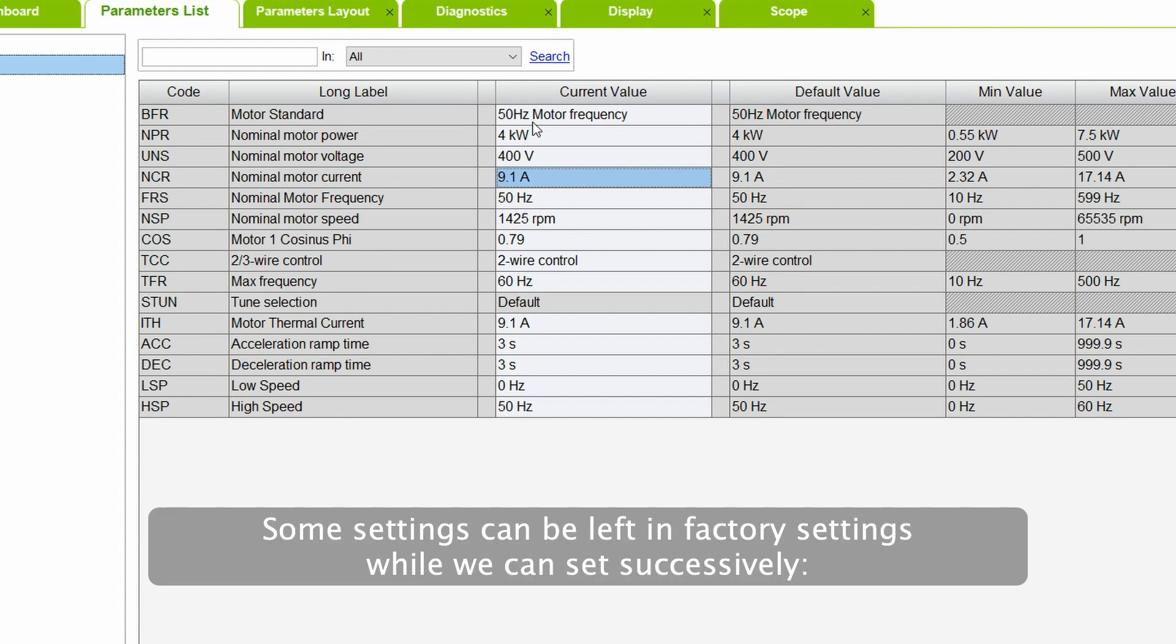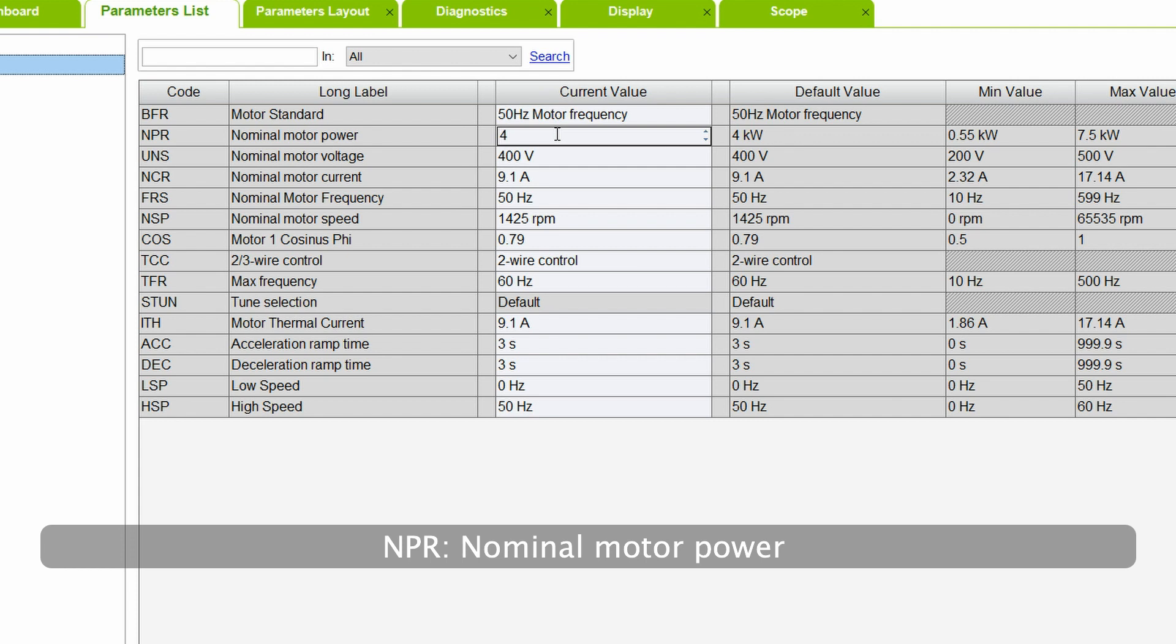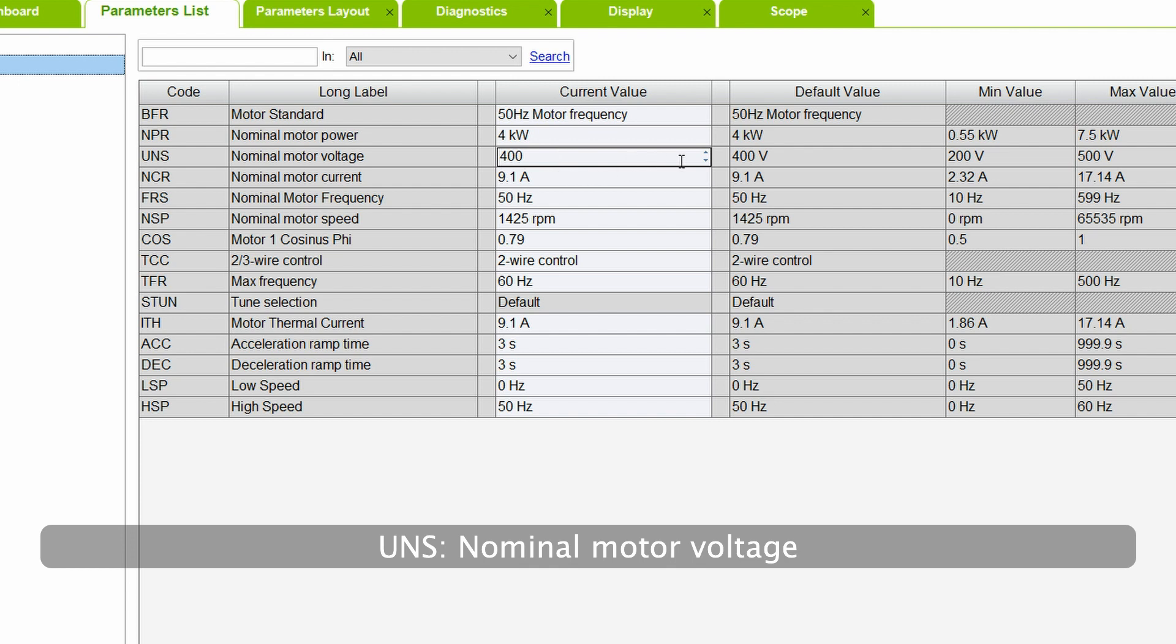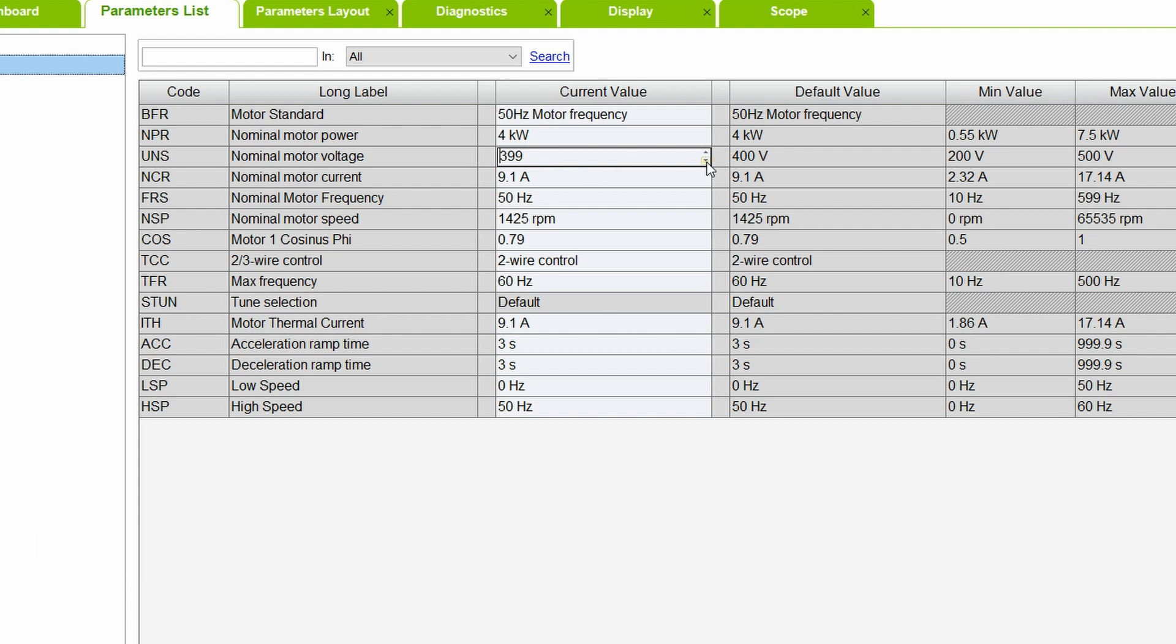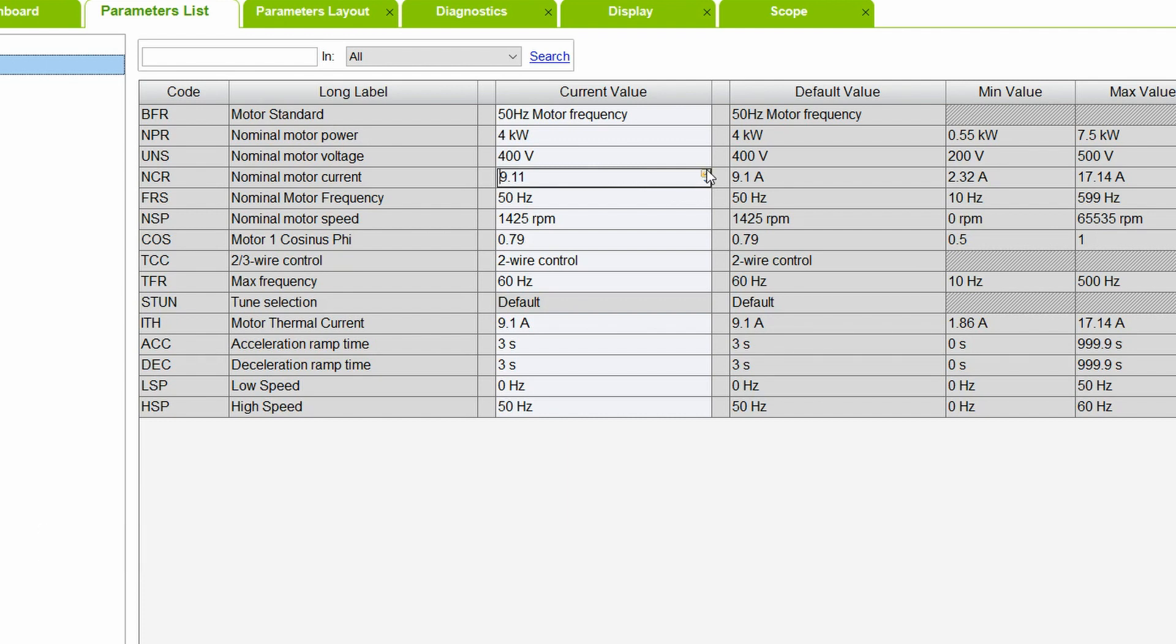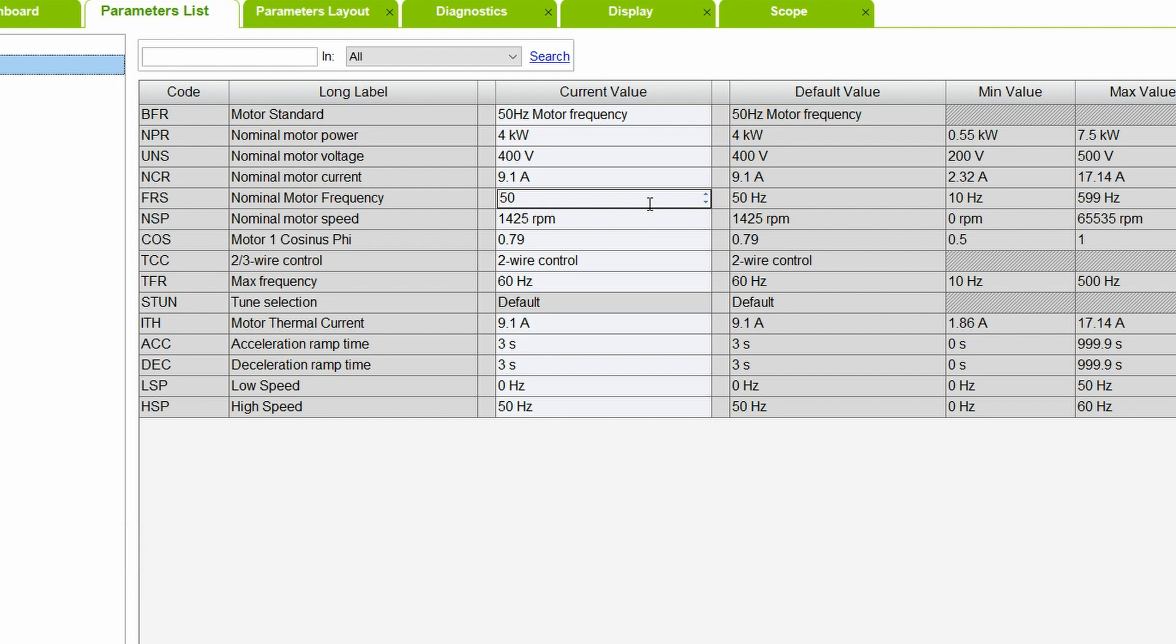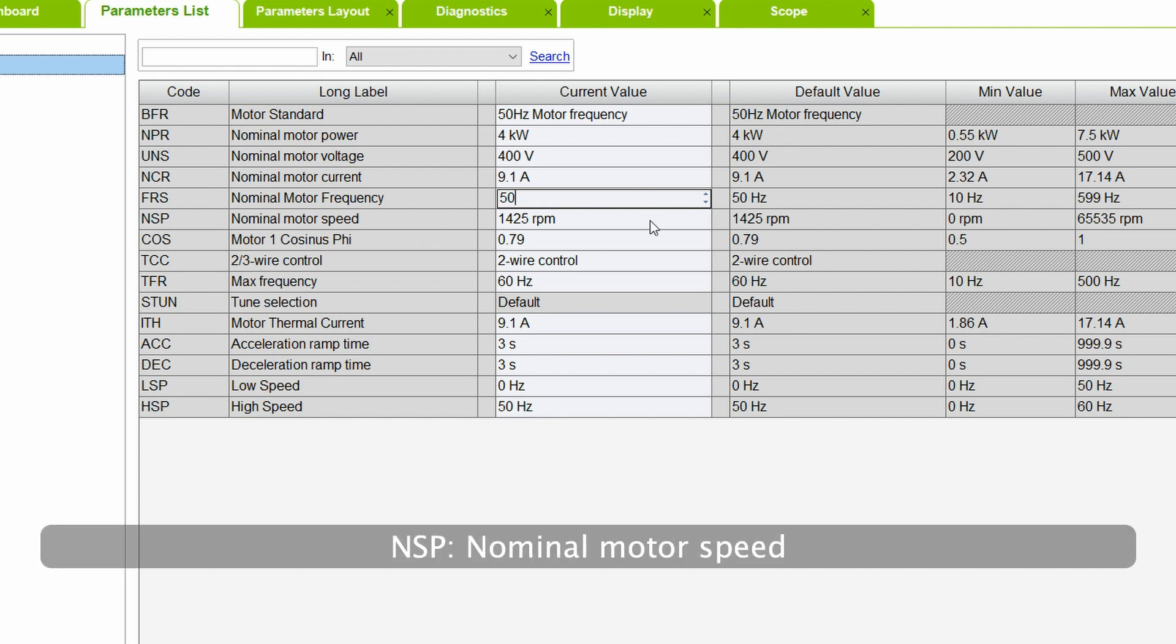Some settings can be left in factory settings, while we can set successively NPR, nominal motor power. UNS, nominal motor voltage. NCR, nominal motor current. FRS, nominal motor frequency. NSP, nominal motor speed.